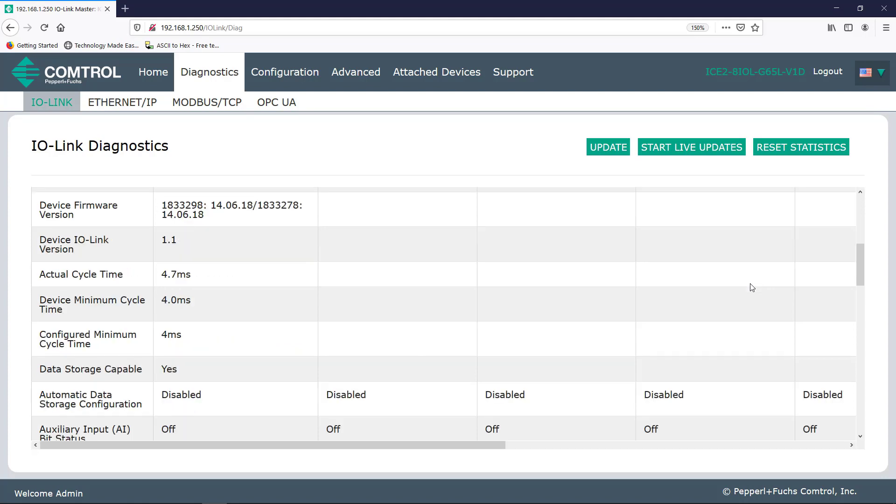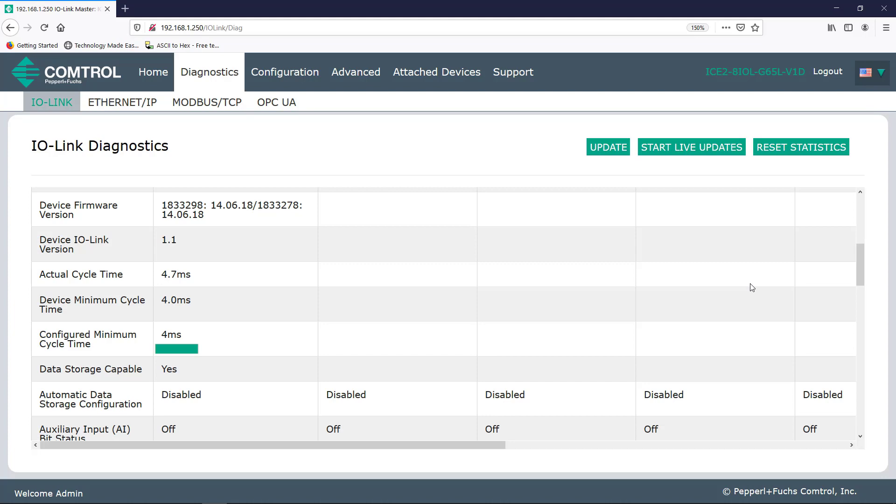Next is actual cycle time. This is the actual or current cycle time of the connected IO-Link device. In this case, my RFID head. This is what it's actually operating at. Device minimum cycle time is the minimum or fastest the IO-Link device could be. And last, we see configured minimum cycle time. This is basically the fastest that the port can operate at.